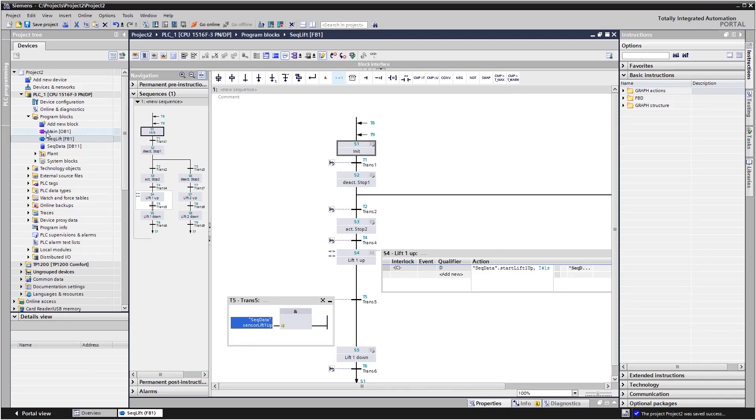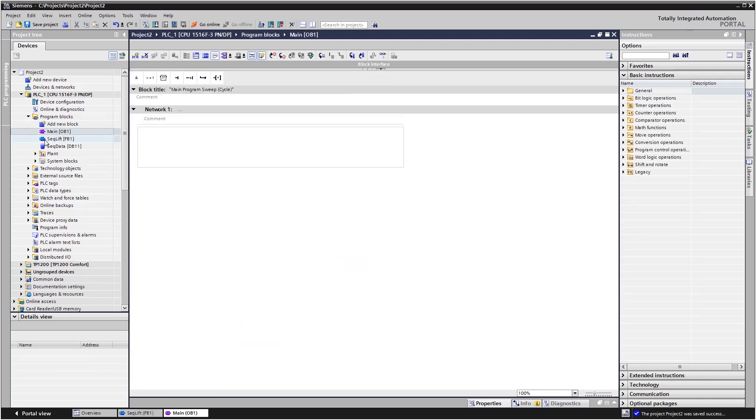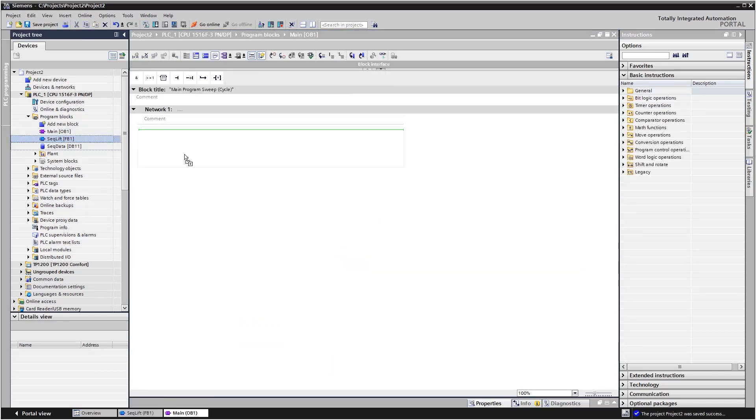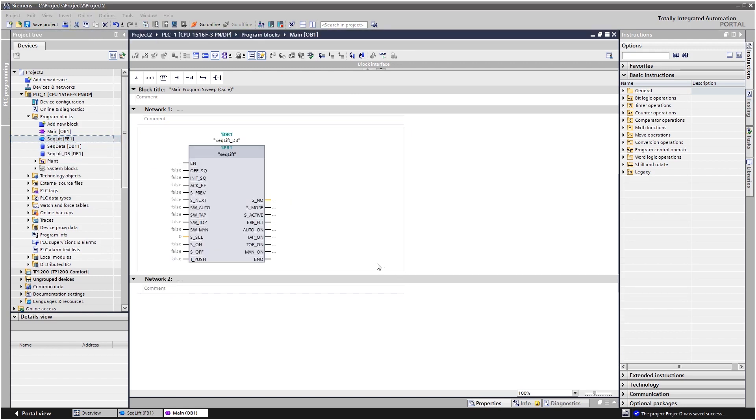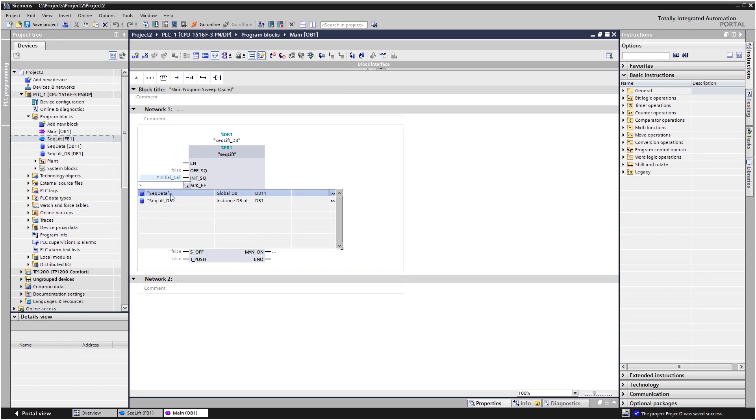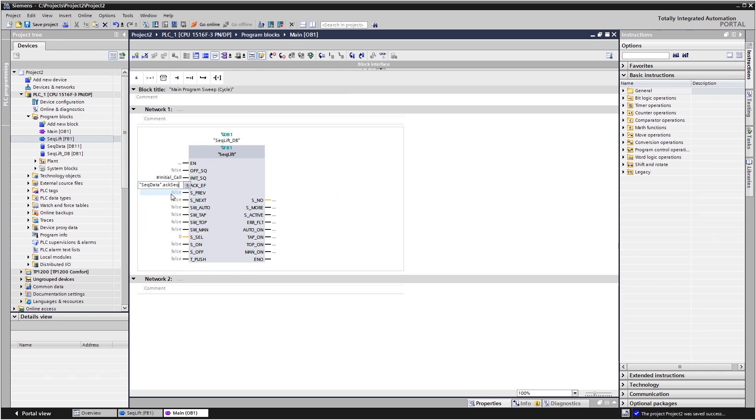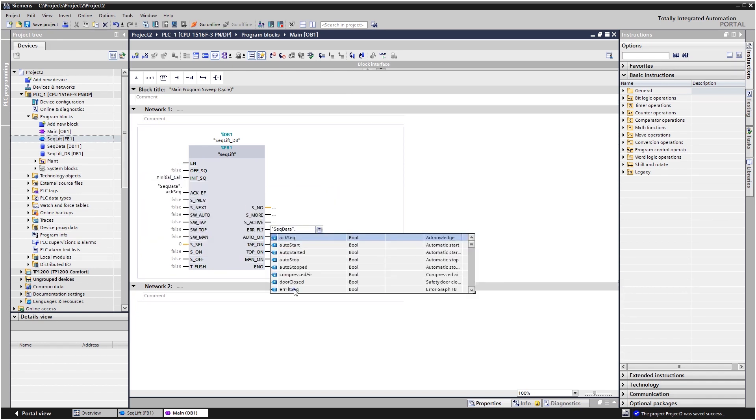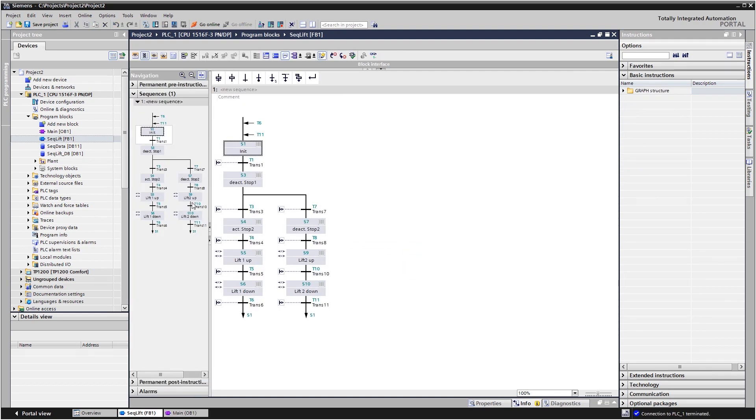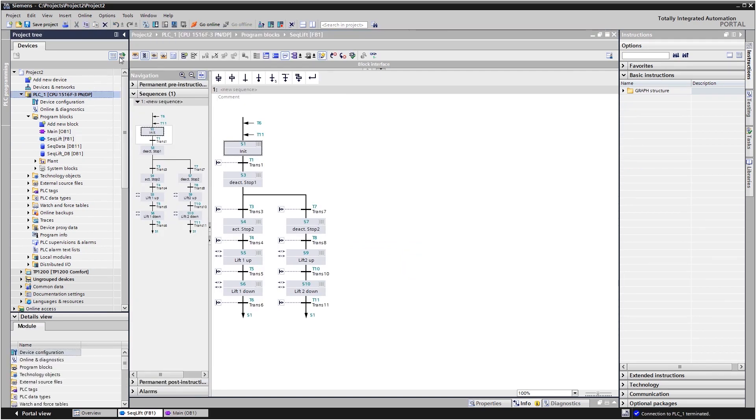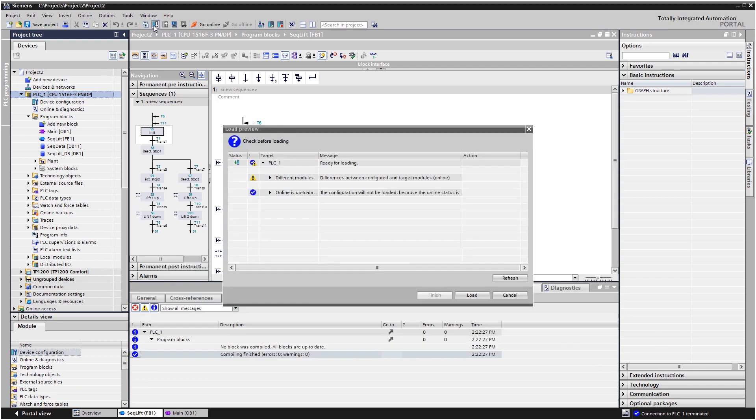The GRAPH FB must now be called up, for example in the cyclically processed organization block OB1. To do so, you need to connect the necessary input and output parameters accordingly on the function block interface. For tests or during commissioning, you subsequently load the project into the controller.